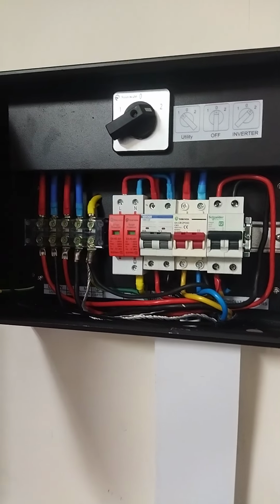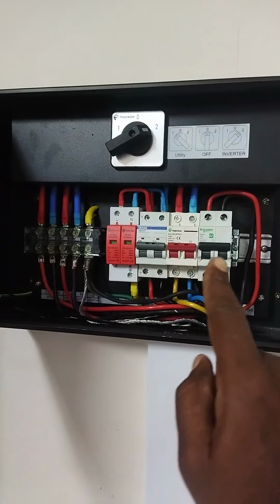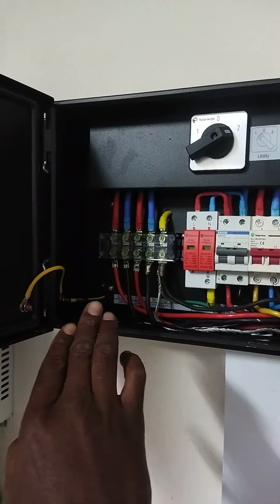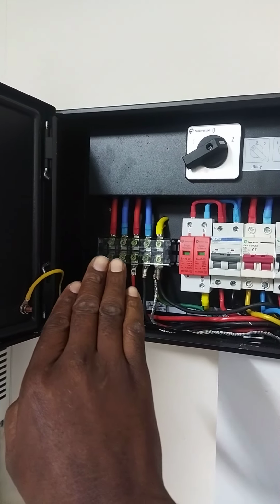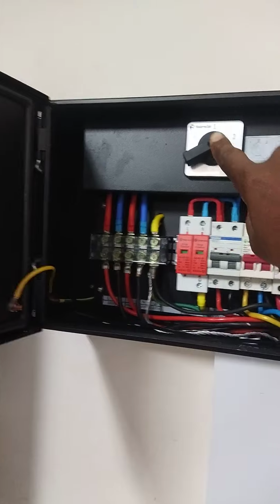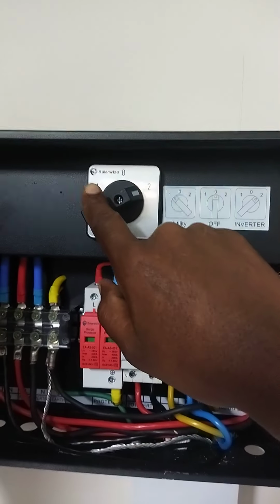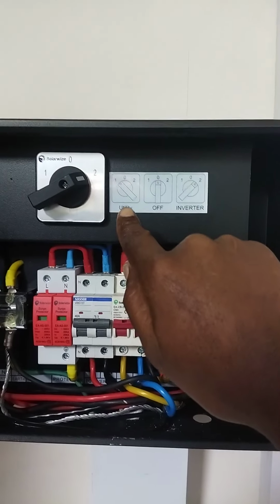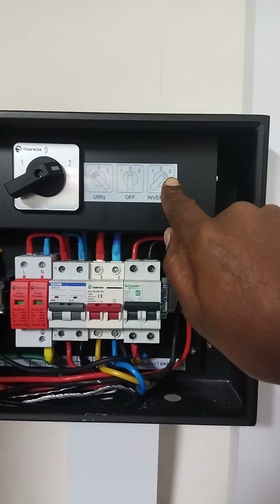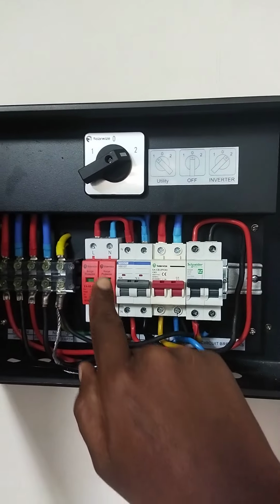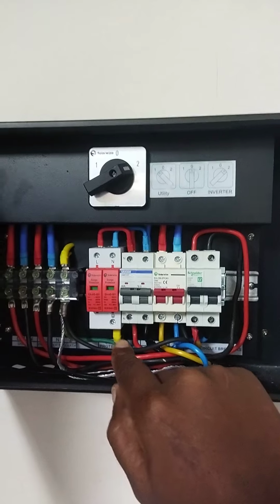So what we've basically done here is we have our inverter input wires coming into that system to the changeover switch, which is a dial system. It's got a 1 and 2, utility is 1, then off, and inverter is 2. And then we've got our SPD to protect the inverter.